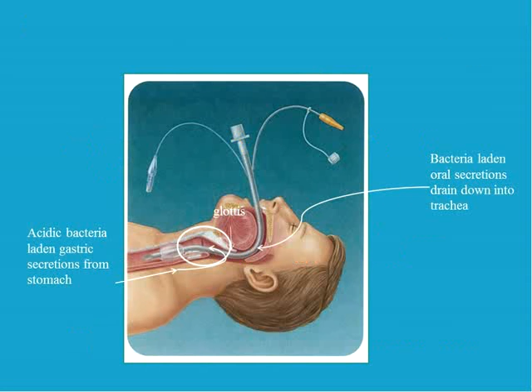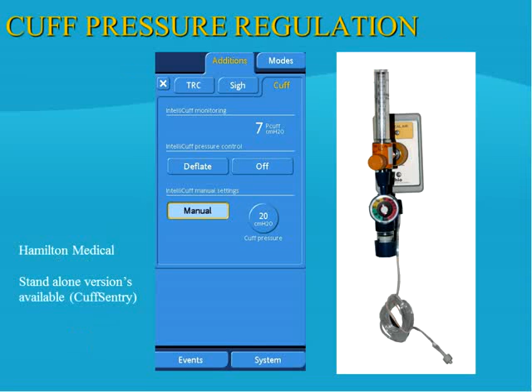So, cuff pressure regulation. There's a high-end solution to this problem, and there's a low-end solution. A high-end solution is that some ventilator manufacturers are now incorporating cuff pressure maintenance within the microprocessing systems of the mechanical ventilator. There's also a standalone version that just plugs into an air or an oxygen flow meter, has an inherent manometer, and will maintain a constant cuff pressure on the endotracheal tube cuff.